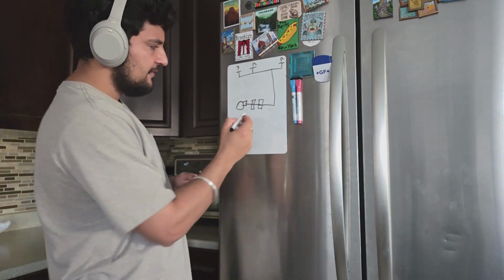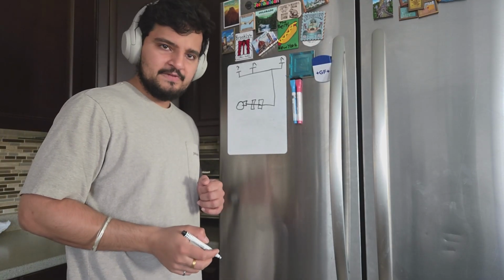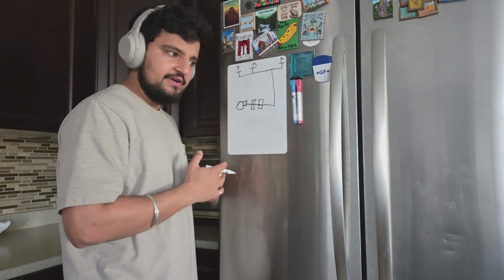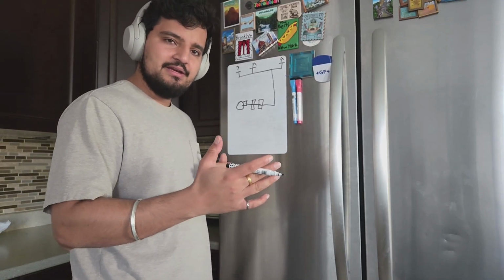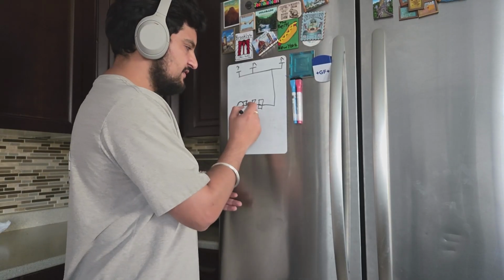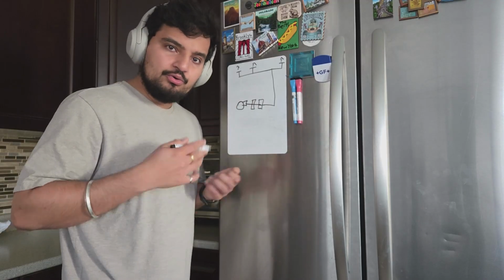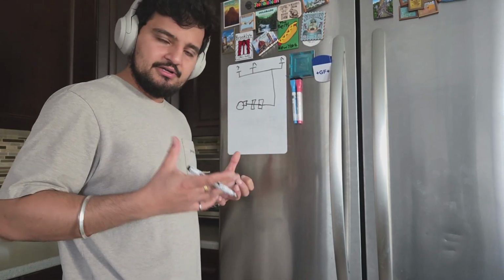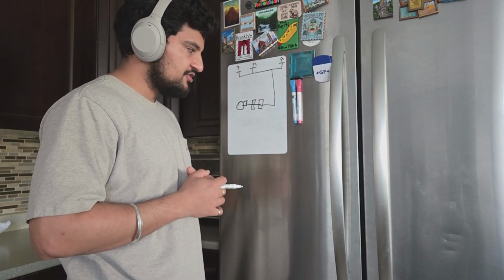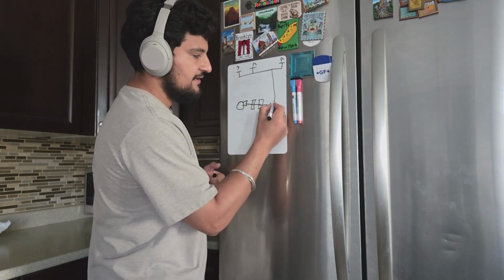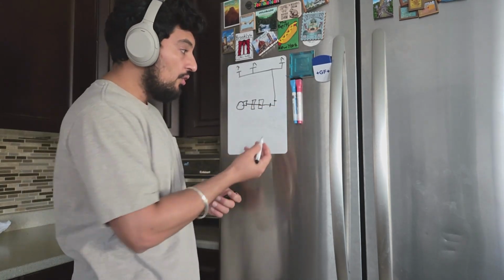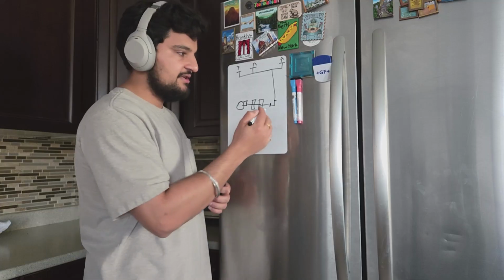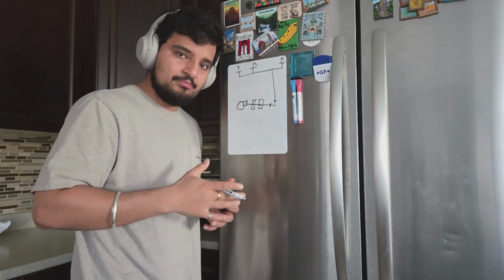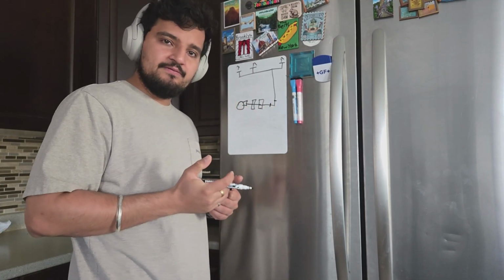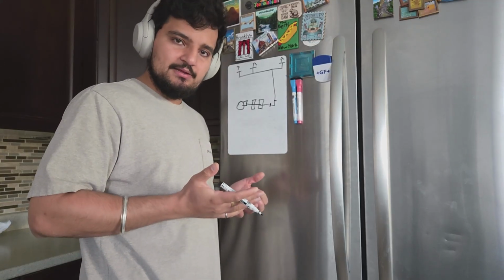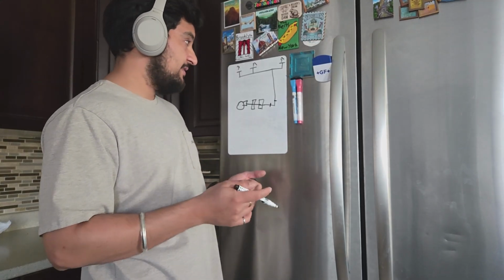So number one, your filter could be dirty, right? When your filter is dirty, it increases the pressure loss across it, and it can reduce your fan airflow, right? So that could be it. There could be some issue with your cooling coil. Maybe there's some buildup of dust and dirt that increases the pressure drop. You could also have some obstructions in the ductwork, or maybe the original designer actually didn't consider the pressure loss across the ductwork properly. So now your fan is actually functioning at a less optimal rate than it's supposed to. So that could be it too.